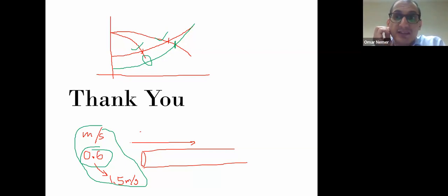Okay. In this situation, we need to be careful. This pipe, once we size it for the worst case scenario, which is the two pumps, I need to check after sizing what about if I operated one pump?